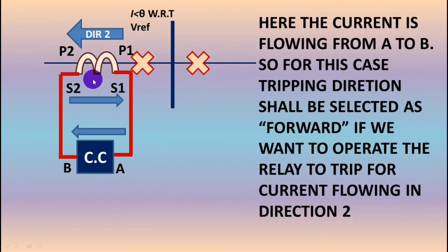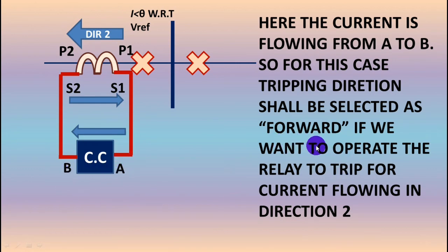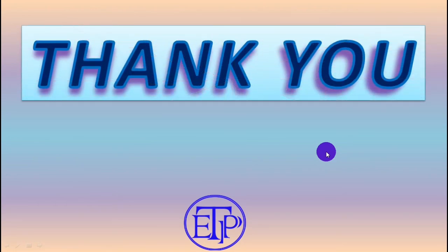Now if you make the relay connection in this alternative way, you have to select forward, because if you want the relay to trip for direction 2, the current is flowing from A to B in this connection — so you select forward. This is how the directional relay detects the direction.